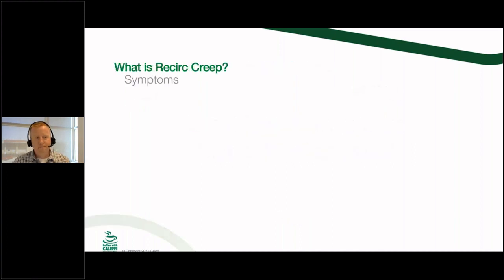So the first thing I want to talk about is recirc creep. And recirc creep is one of those things that happens, and you may not have heard this particular terminology or this particular idea, okay? But what I wanted to start off with was the symptoms. And the reason why I wanted to start with recirc creep first is not only can it be problematic, it can make you think your mixing valve has gone bad or something's going wrong in the system, but it's also a potentially dangerous situation for the occupants of the building. And so not only can it just cause you callbacks and things like that for your service contractors, but it can cause lawsuits and all kinds of other not so fun stuff.